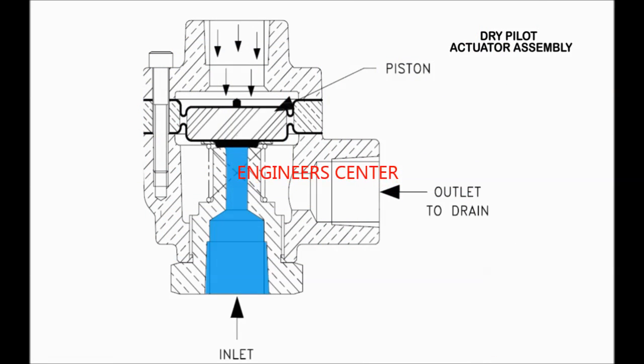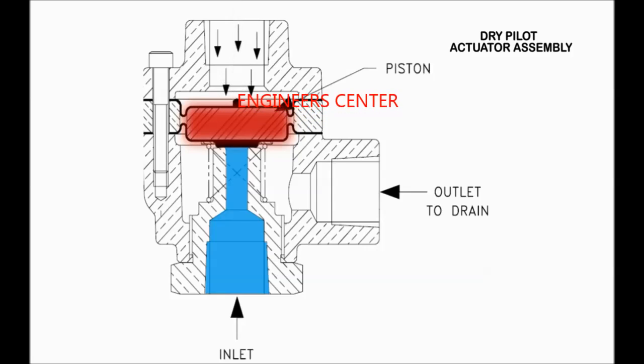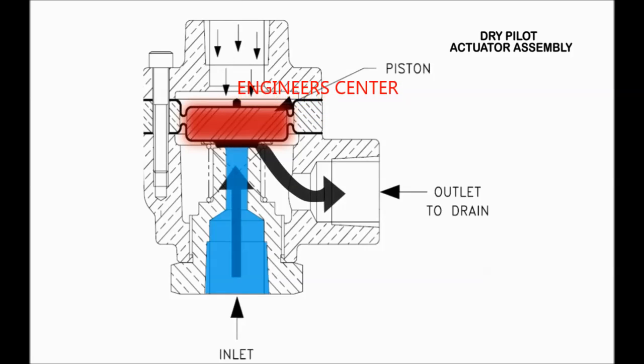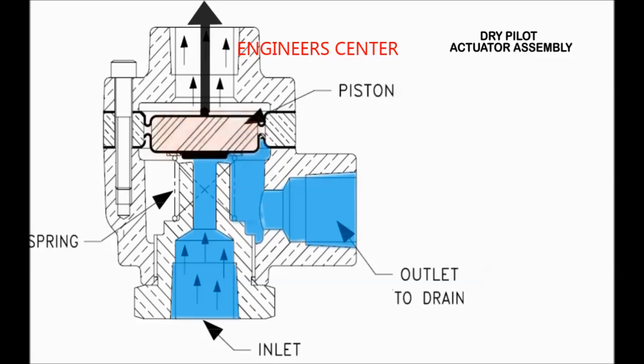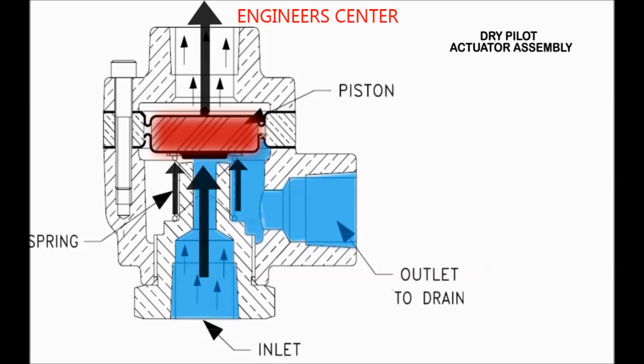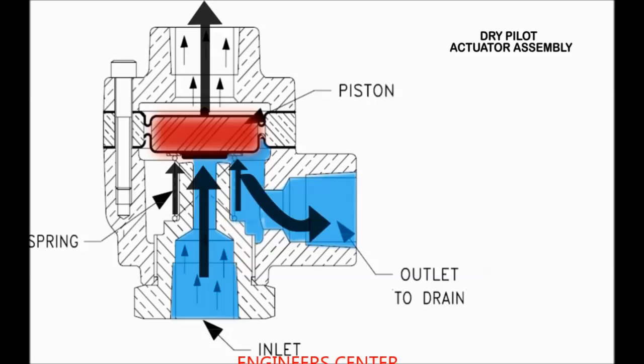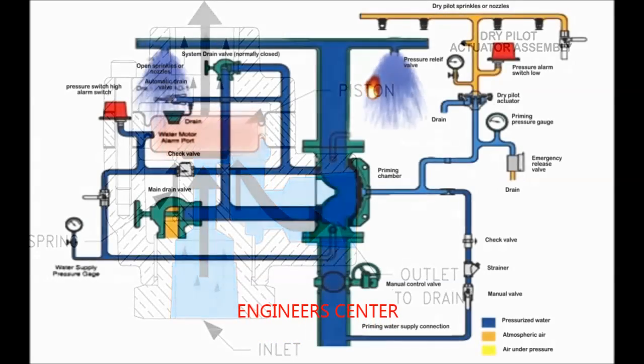Here is a diagram explaining the internal operation of the dry pilot actuator. In the shown figure, the valve is in the closed position where pressurized air on the piston and diaphragm assembly works as a seal between the inlet and the outlet of the valve. When activated, the pressurized air above the piston is released, and the water pressure together with the spring force pushes the piston and the diaphragm assembly upwards, allowing water to pass from the inlet to the outlet drain, consequently depressurizing the priming chamber pressure and activating the deluge system.